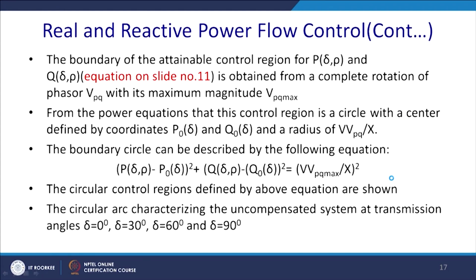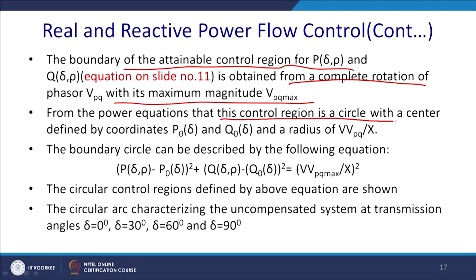So, as shown in the equation in slide number 11, the boundary of the attainable control region P delta rho and Q delta rho is obtained from a complete rotation of the phasor VPQ with the maximum magnitude of VPQ max. From the power equations, this control region is a circle with a center defined by the coordinates P delta and Q delta, with radius VPQ by X, which equals 0.5, generally chosen. Thus, what happened? The boundary circle can be described by the following equation.